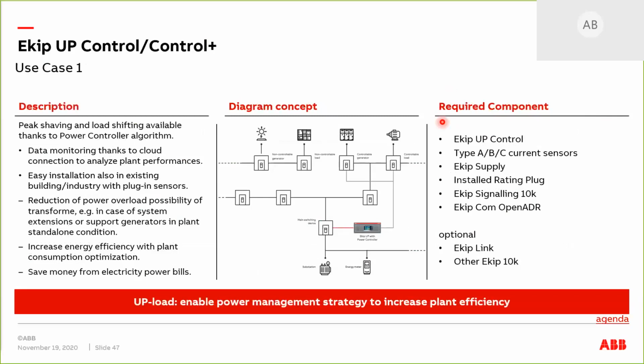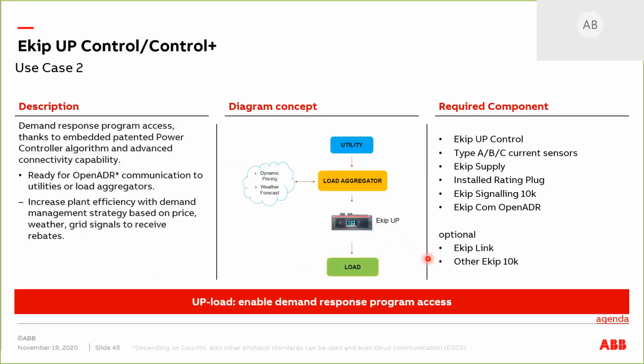All right, so this one is the control. With the control system, the Ekip UP Control is used for the peak shaving and load shifting capability, with the embedded algorithm that we put in the EKIP app. Since there are three: the EKIP monitor only monitors, the EKIP protect protects, and then the EKIP control controls the breaker. So with the Ekip UP Controller, this is just one system.